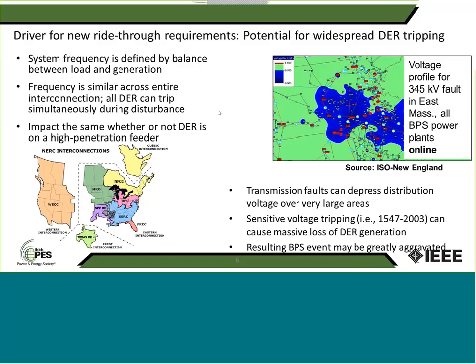So yes, the fault will go away, but the impact on the system can stay. Because of the inductive characteristics of the grid, you may see a voltage recovery of the system at a low speed.